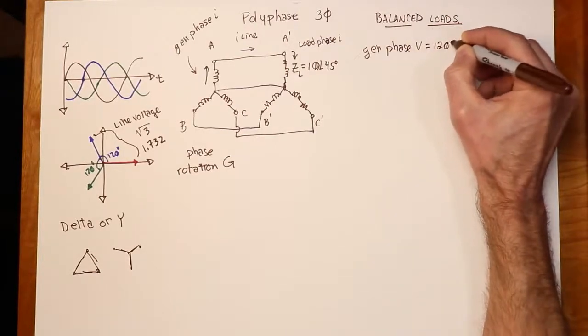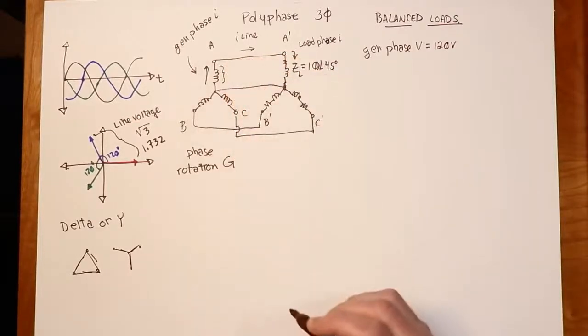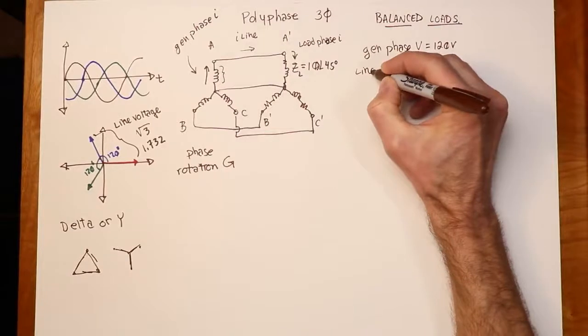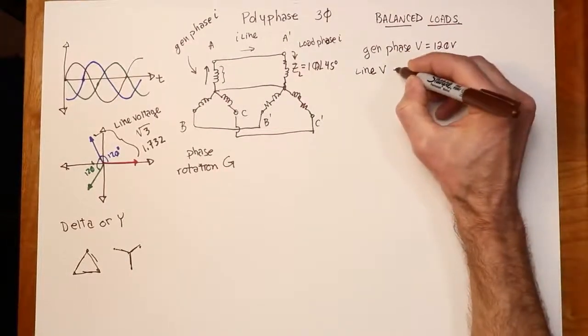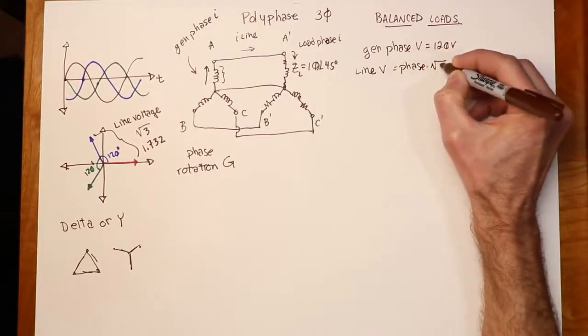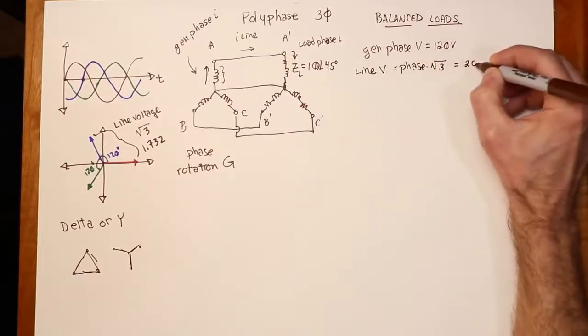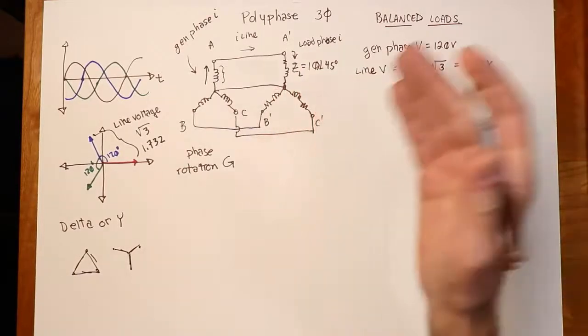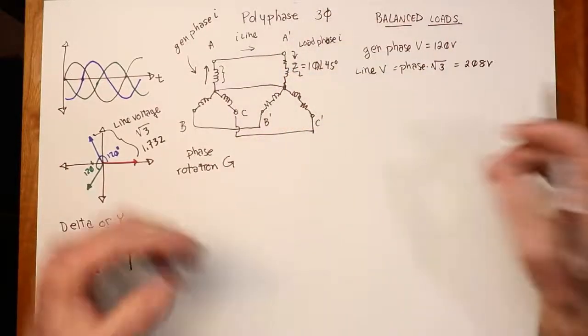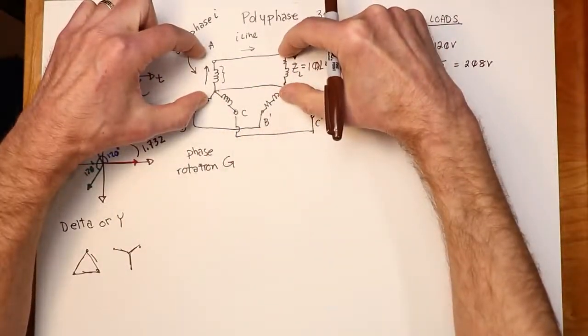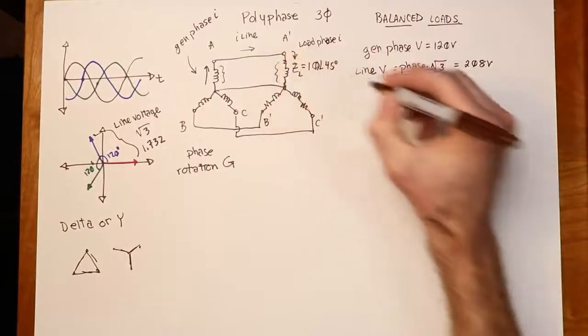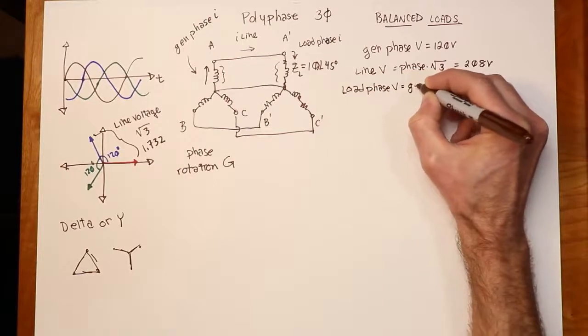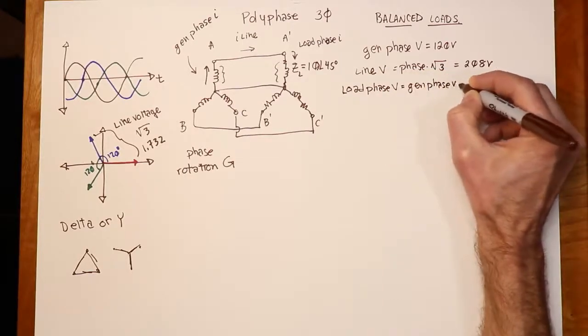If we start with a standard 120-volt North American system, the generator phase voltage is 120 volts out at each terminal. Then the line voltage from terminal to terminal would be the phase voltage times the square root of three. Multiplying: 120 times √3 equals 208 volts — a very common three-phase line voltage. In Y-Y configuration the load phase voltage equals the generator phase voltage, which is 120 volts, because the neutral connection forces them to be equal.